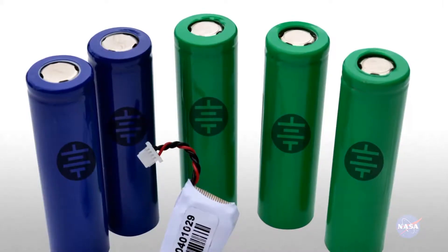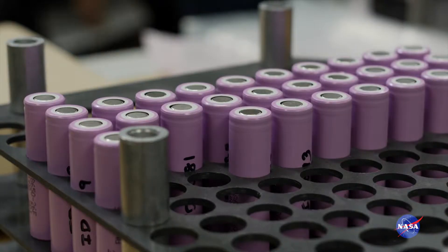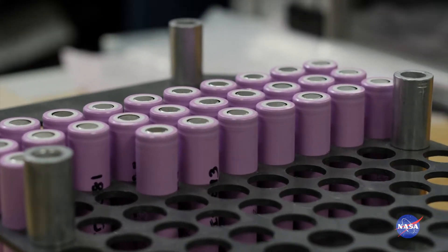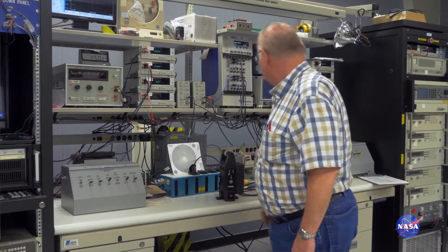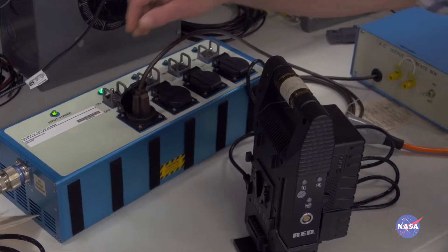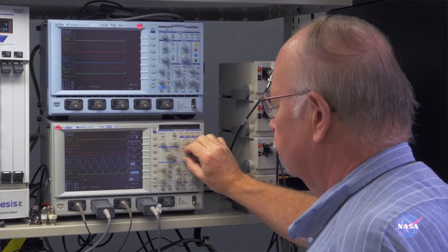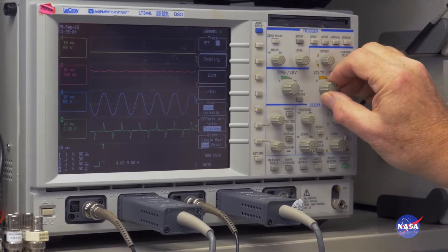This technology has a high reliability because it does not introduce a lot of extra components into the battery and it has a small connector pin count. The circuit is designed to measure individual cell and battery bank voltages and provide balancing current to cell banks that need a little equalization. It also has the advantage that it's got built-in electrical isolation.